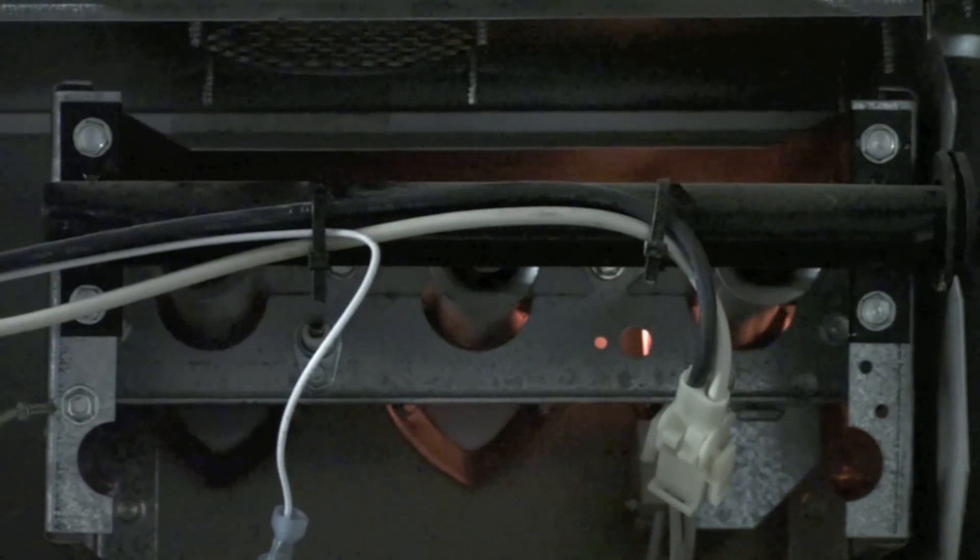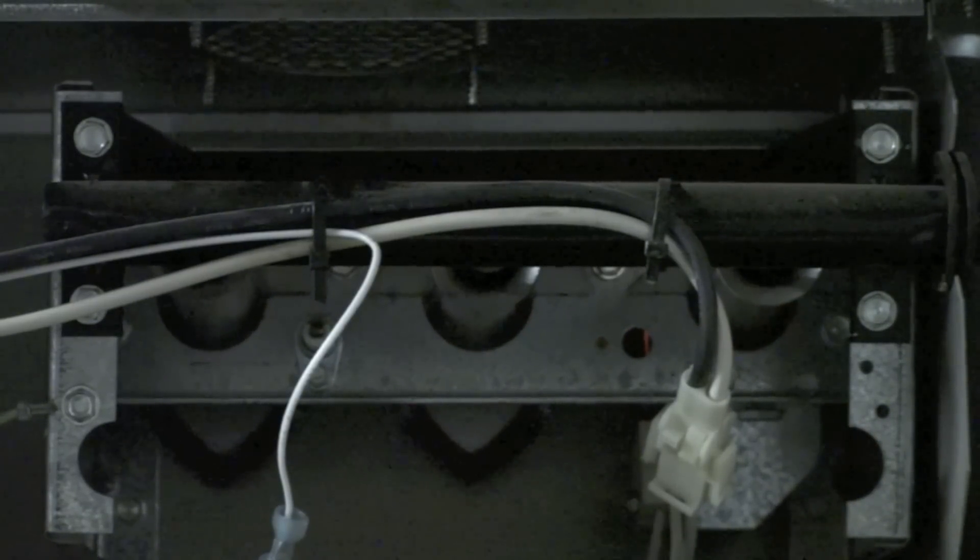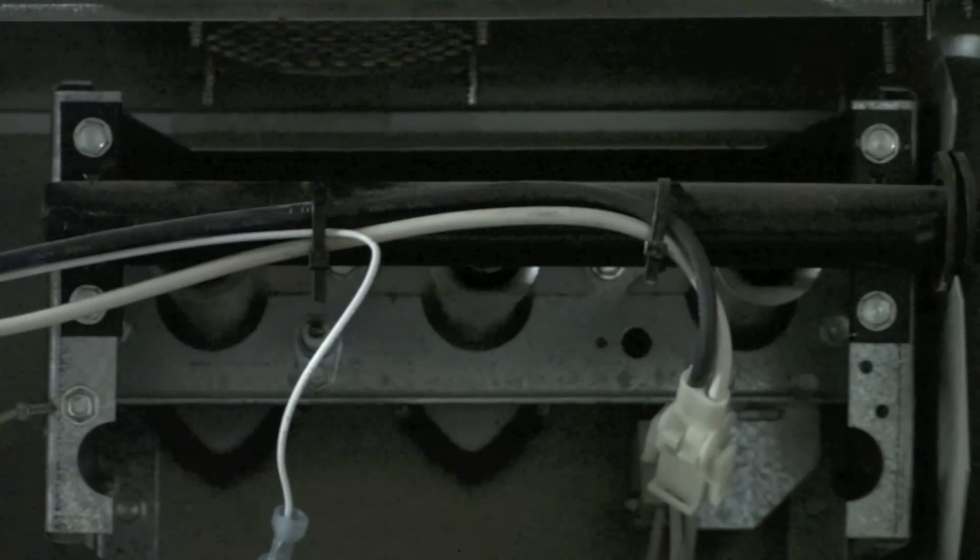Okay, flame went out because there's no flame sense. Now this hot surface igniter will come on again and it'll go through that same cycle. I'll let it run through one more cycle and you can see how it works.